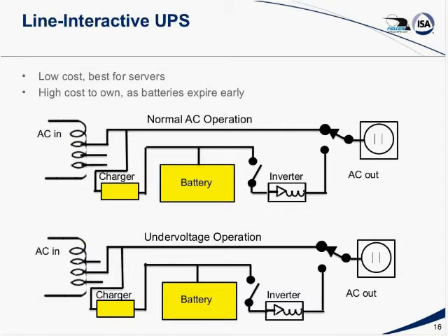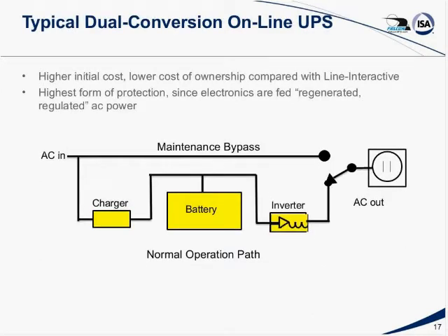Now, we had a question, and here's an answer to the question. What is an online UPS? They're called dual conversion because they actually do two conversions. If you look at the diagram, you'll notice it looks a great deal like the offline when it's in the power mode. That is true because the inverter is running 24/7. You are running your loads completely off of the inverter, which in turn is being supplied by the battery. The charger charges the battery when the AC line is on. You never know, much like a laptop computer, if the power is plugged in or plugged out because the inverter is supplying the power at all times. Now, this does require a higher initial cost because the components have to be rated to operate 24/7, and they have to be rated at the temperature range you're going to operate at, along with the batteries. But that is what is meant by an online UPS.